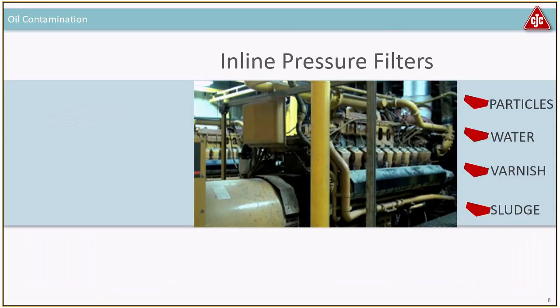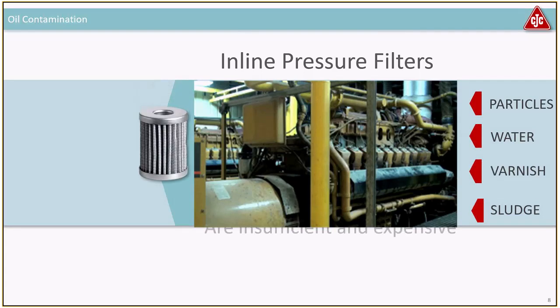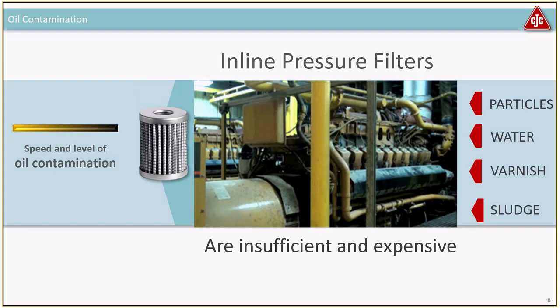If you have questions, you're welcome to type them into the instant message field. Many machines already have an inline pressure filter built in, which primarily takes care of particles, but they're not designed to keep the oil clean and make it cleaner over time. Very often the oil will actually become more and more contaminated. Inline filters do not remove water, varnish, and sludge — you're only focusing on particles. A very fine inline filter, like a 3 or 5 micron filter on a turbine, can be very expensive to run.